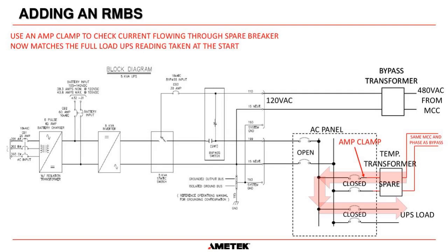So you can put 10 panels on there, but that means each panel can only supply half a kVA, because all of the panels would add up to 5 kVA. Or you could have 5 panels, one could be 4 kVA and the other 0.1 kVA. There is no restriction on how many panels can be connected. It would just get cumbersome trying to mount all of those cables into the UPS terminals. So there is no limit as long as you stay within the rating of the UPS.